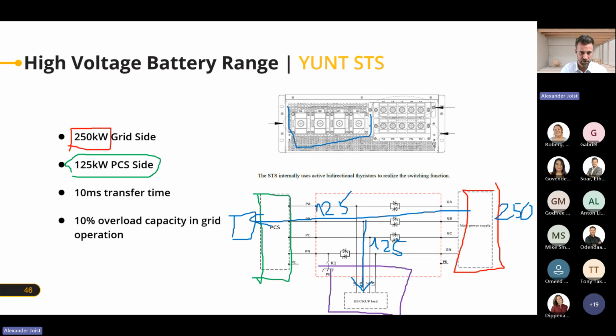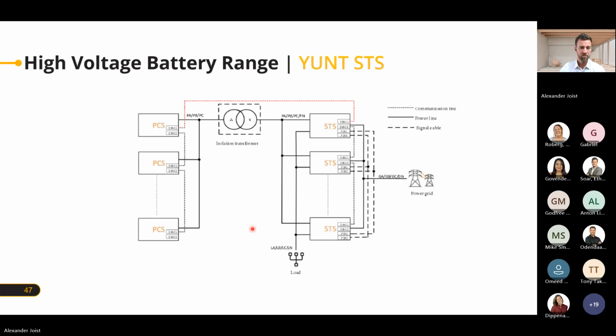And you can see also these are the grid connection points. They have much bigger connectors than the other two connection points for loads and your PCS, right? But this 250 kilowatt STS is only made for a 125 kilowatt PCS and 125 kilowatt loads, right? Just so everyone understands this. Then now if we have multiple, as we said earlier, if we're using multiple products or building bigger systems, especially with STSs, then we're going to need a transformer. Also important is we can do up to 2 STS maximum.